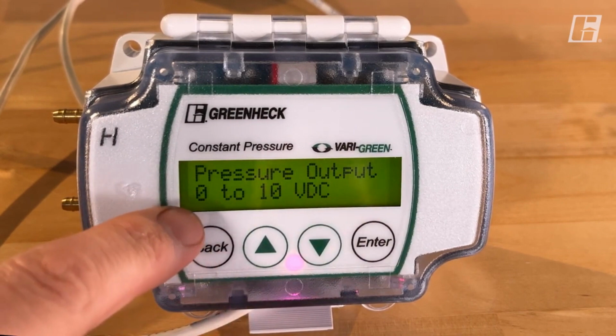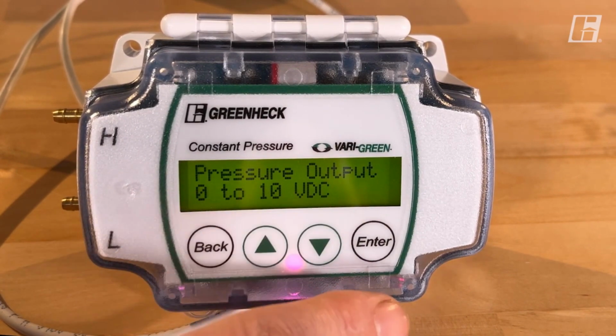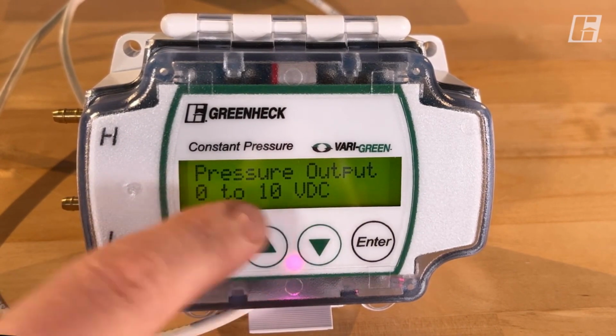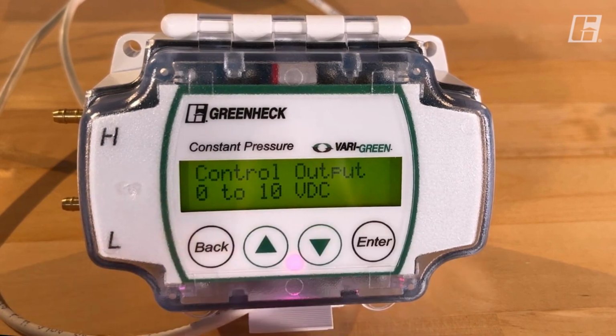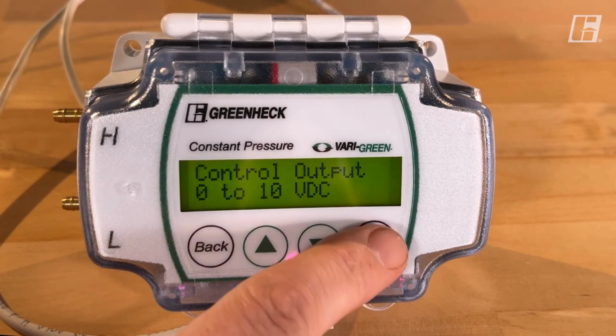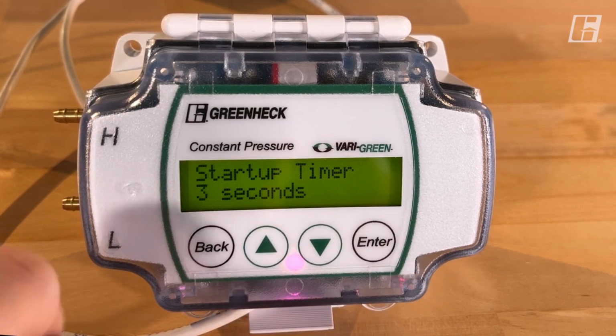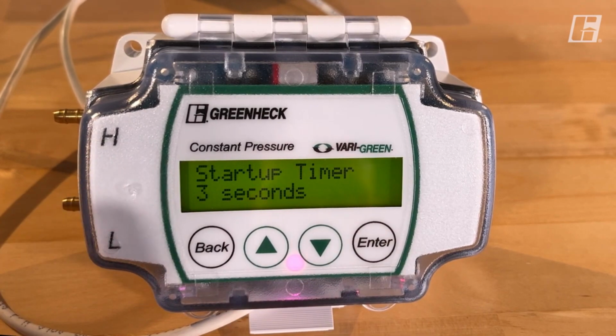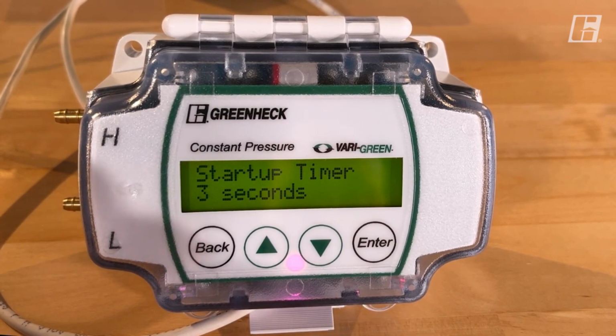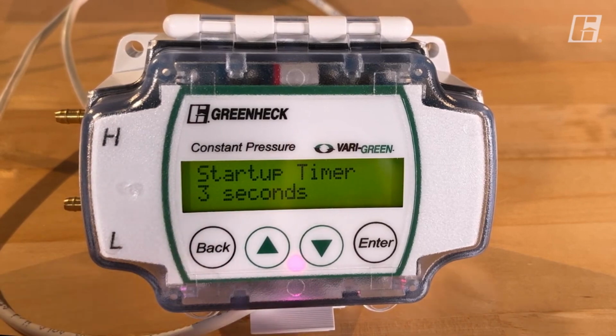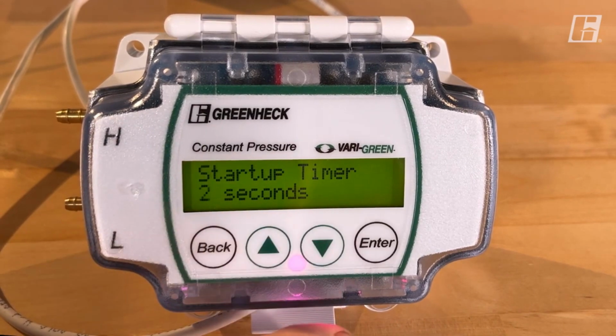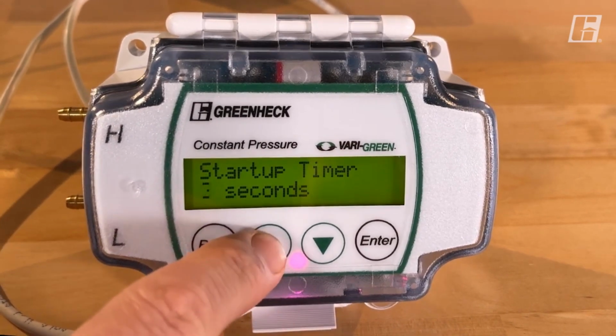Pressure output, this is from the factory 0 to 10 VDC. That is what our motor is designed to read. Then it gives us a startup timer that gives you a couple of seconds delay before it starts controlling, and you can modify this. 3 seconds is standard.